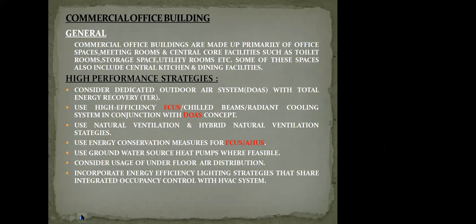So in such cases, we can assure induction of fresh air through DOAS, because we can get the outlet humidity of the DOAS to the extent of 40%, 35%. So you are maintaining the temperature above the dew point temperature and giving fresh air at around 35-40% humidity, and that eliminates the total possibility of condensation. So that we should think. But if it is not Calcutta, had it been Delhi, then we need not go for DOAS. There we can go for some other system for fresh air induction, because there humidity is not the main factor.